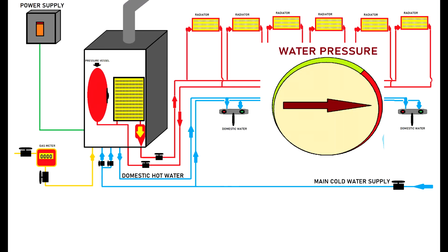As I said before, if the installation is too big, there might be nothing wrong with the boiler and the pressure vessel, yet regardless of how much you want to pressurize it, you can't. If you heat a large quantity of water and you don't use the appropriate pressure vessel, or an extra pressure vessel to take off the extra volume generated by the water when heated, then the pressure will go into the red side, as you will see on this gauge, and then the pressure relief valve, to protect you, will allow the excess water generated by the pressure to leak from the boiler. Here you will see the relation between the pressure vessel and the higher pressure, but as I said, it's not necessarily a wrong pressure vessel.